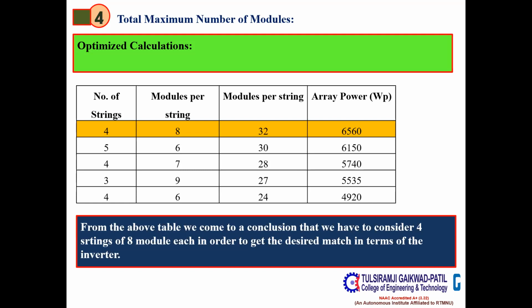So from this table, what we can conclude here is, as the inverter size provided to us is 6700 watt, or in other words 6.7 kilowatt, the first sizing that is highlighted with the yellow color, that is 4 strings, maximum number of modules per string as 8, and total number of modules as 32. This would be the optimized selection, or the optimized calculation which we would do in order to match the array output with the inverter specifications. So this was the core part of our today's expert session, and I hope I am being able to convey the calculation part and to solve the particular problem statement.